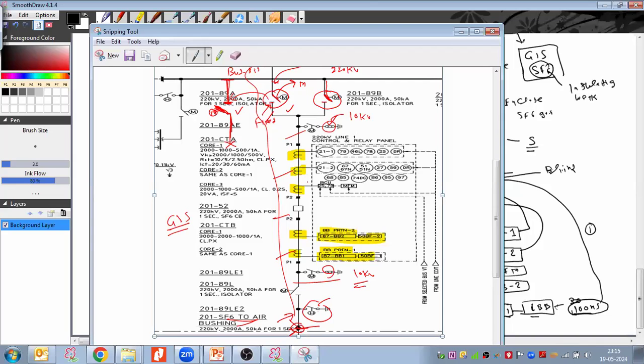In some cases the client says to use the circuit breaker in all cases, for both the bus riser as well as the bus coupler. And in some cases the client says there is no need for a breaker, only go with the disconnector, right? Is there any specific standard? No, there is no specific IEC standard. This is a project-to-project, client-to-client requirement. There is no such IEC standard.